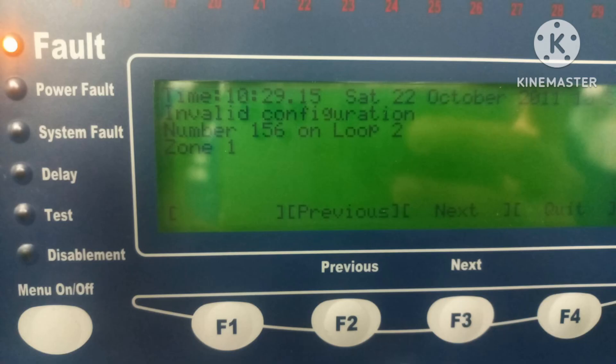Thanks for watching. If during commissioning you didn't put any valid state for the device, your panel will show invalid configuration. In that case, go to that device — for example device number 156 — check what state is set there, and then change it to the desired valid state. For smoke sensors, valid states are 0 to 3. Thanks for watching.